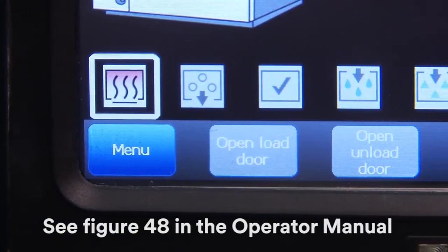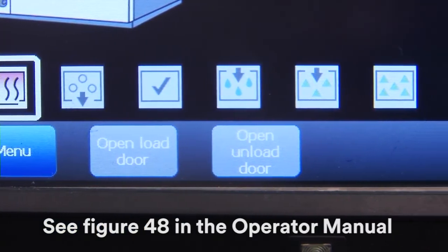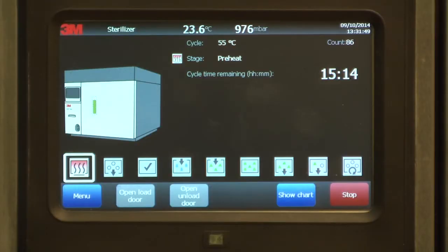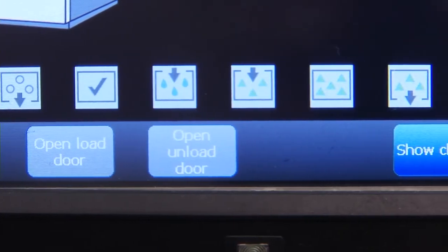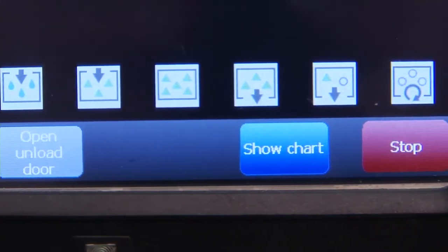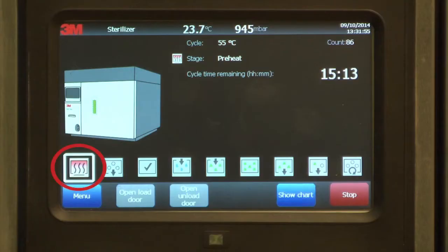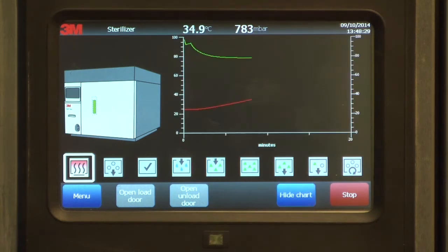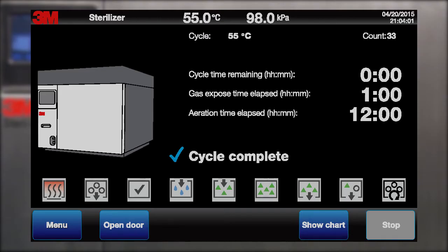The screen will display the progression of the sterilization cycle beginning with the preheat stage. The screen also displays the cycle name, current cycle stage, cycle count, and total estimated remaining cycle time. The bottom of the screen contains the cycle stage icons for the sterilization process. A white box around a stage icon indicates the current stage. There's also a screen option to display a real-time cycle chart of temperature, pressure, and relative humidity during the sterilization process. When programmed aeration is complete, the Cycle Complete message will display on the sterilizer touchscreen.